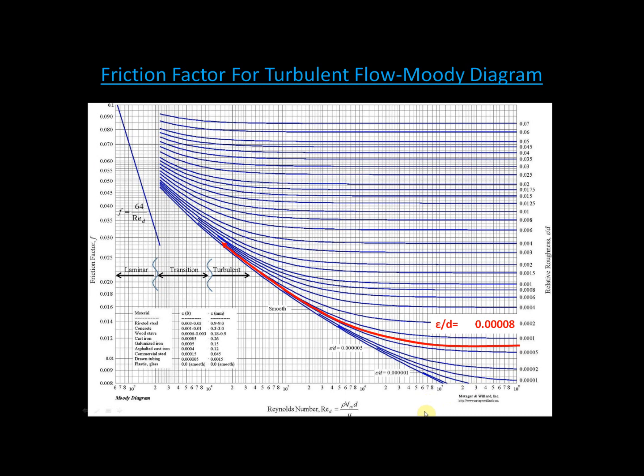Now, I can also compute my Reynolds number. So let's say I compute my Reynolds number, and I get approximately 1.4 times 10 to the fourth. Well, that tells me I'm in the turbulent region because I'm greater than 10,000. So I'm going to index here on the x-axis that Reynolds number. An important thing I want you to note, besides the fact that it's logarithmic, so it's not as clear just going, oh, here it is, it's right in the middle, you've got to look at how everything's spaced out. So if you get confused in how things are spaced out, let's start here. 10 to the 3, so that's 1,000, right? This is 2,000, 3,000, 4,000. You can see the gap between 1,000 and 2,000, how it continually grows smaller between 3, 4, 5, 6, 7, 8, 9, and then 10,000.